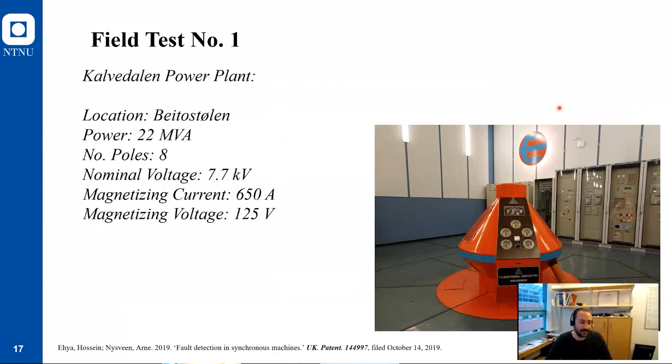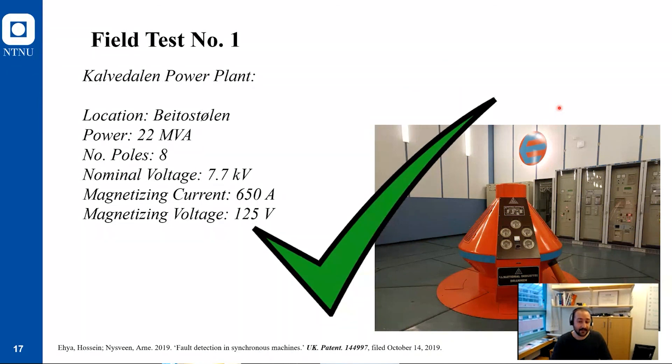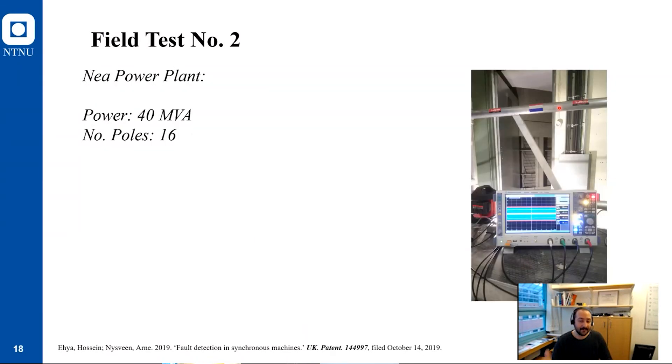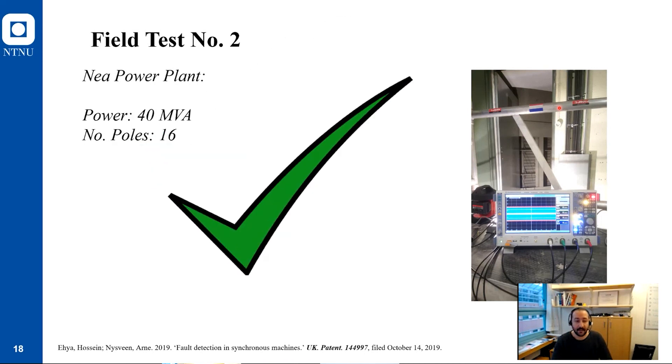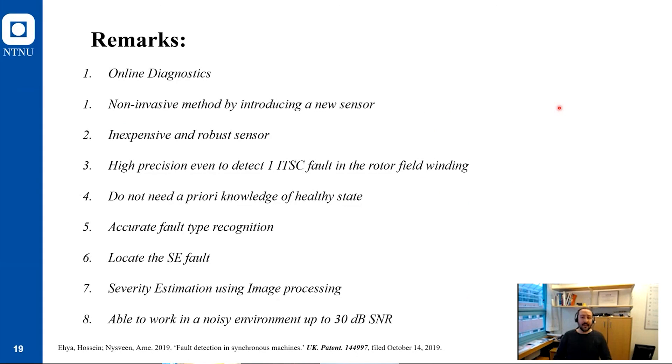We had a chance to perform a test in the Kalvedalen power plant. It's a 22 megavolt ampere synchronous generator. It has eight poles, but this power plant only has one unit. We performed the test. We installed the sensor. It was really quick measurements. We performed all the measurements in less than one hour. After we analyzed the data, we were able to detect the fault in this machine. This field test also worked well. It means the idea is working in a real power plant. But as I mentioned, this power plant only has one unit. Maybe if you're in a power plant with more than one unit, the noise from those could interfere with results. We performed the test in another power plant with different topology with four units, and we were able to detect the fault in this power plant as well.